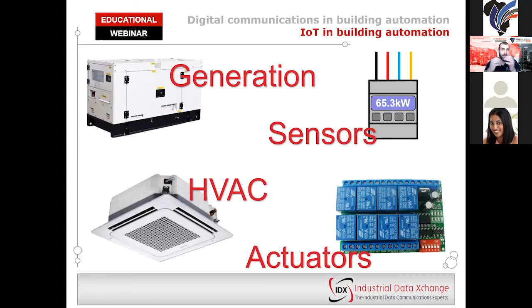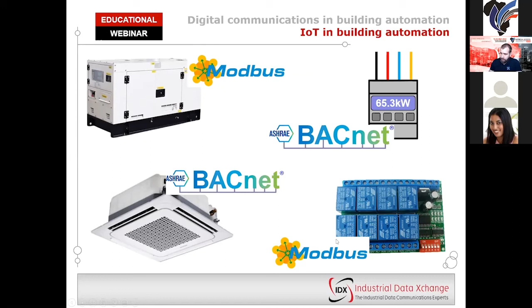As I mentioned, very often these type of systems have communication interfaces already built into them, straight out of the shop. So in this case, my generator at the top has a Modbus interface. My power meter has a BACnet interface, as well as my air conditioning unit. And my lighting controller over here, which can turn lights on and off, also has a Modbus interface.